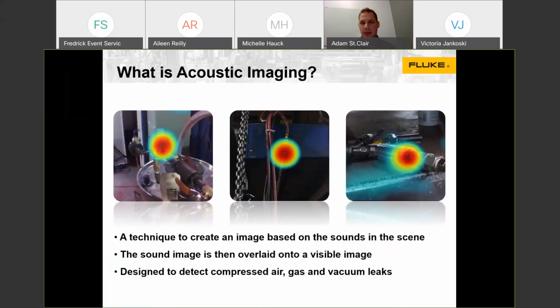So acoustic imaging is really what you see on the pictures across the top of this slide. It's a visual representation of sound. These images across the top of the screen are actually images captured with an II-900. So you see a visual representation like what we see with our eyes in a field of view. And then you also see that target in the center of the screen that looks kind of like a thermal image. What that is, it's a sound map.